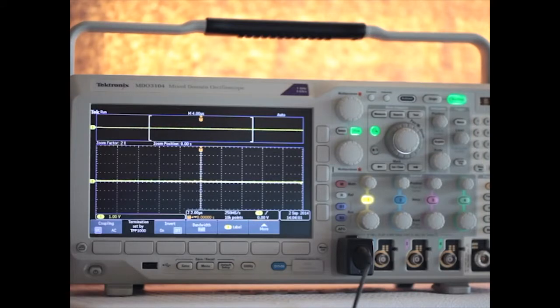Care must be taken when using a bench-type grounded oscilloscope. Don't connect the probe ground reference lead to a circuit node that is floating at some voltage with respect to signal ground. The ground reference lead may, however, be connected to a point that is totally isolated from ground potential. To emphasize, the signal ground and oscilloscope ground must not be at different voltage levels, or there will be a direct short circuit. If this happens, at the very least the probe ground reference lead will burn up, serving as a fuse to protect the rest of the ground path. An alternate scenario will involve extensive damage to the oscilloscope and/or to the equipment being examined.